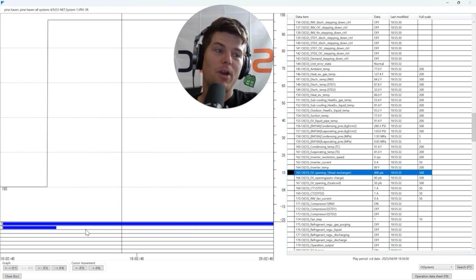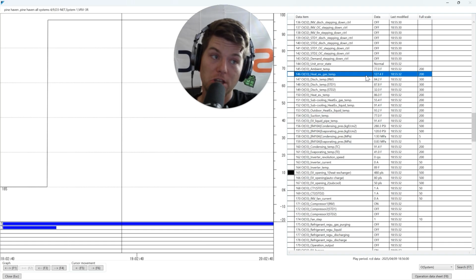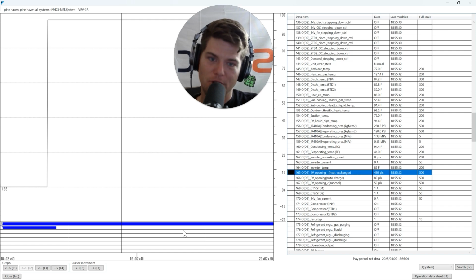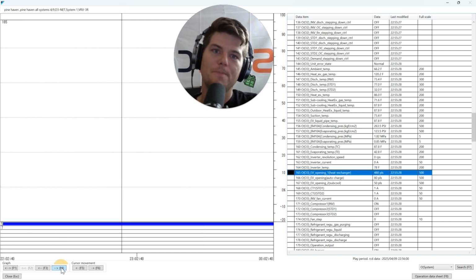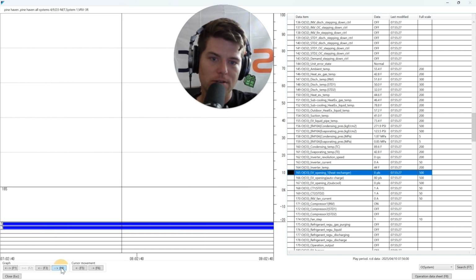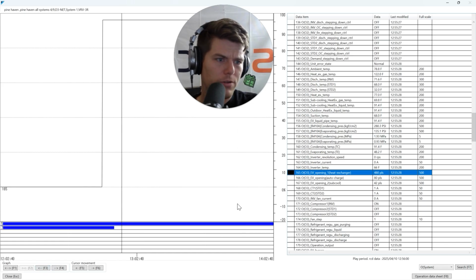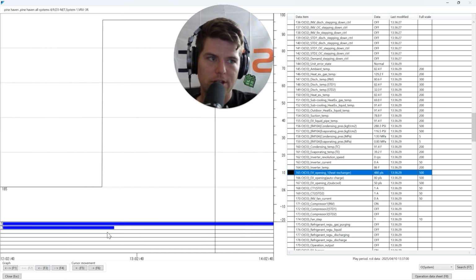Does it use, whoa, here we go, 480 pulses. Okay, well, let's see here. 480 pulses, wide open, not a good thing. However, heat exchanger gas temp 127. So we at least know the refrigerant's going in the right direction. In cooling mode, it does go for full open, so that's not unusual. Does it use it for anything else? And the answer is no, right? When it switches modes, sure, we're back into cooling again, sends hot gas.